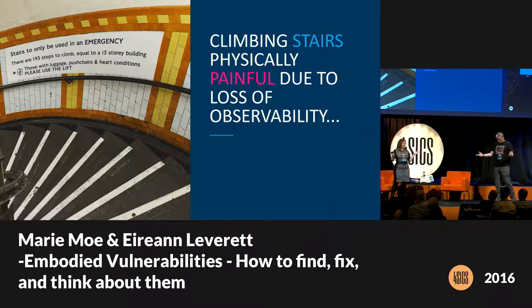And the problem was there was a bug in the programmer HMI. So when the pacemaker technician was looking at the settings, it calculated the upper rate limit, which in my case was 160, but it didn't say 160 on the screen. So there was kind of loss of observability.